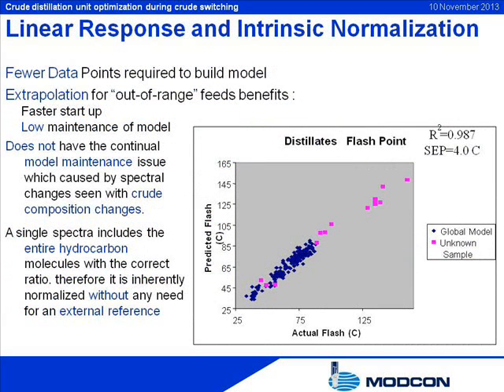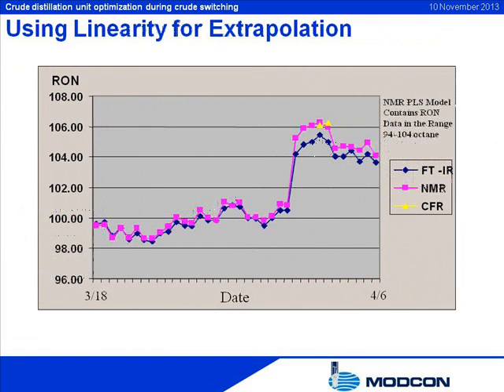The main advantage of this innovative process technology is linear spectral response across a broad range, which enables models to be extrapolated accurately. An NMR analyzer calibrated for a range of 94 through 104 octane gives accurate results also at values higher than 106.